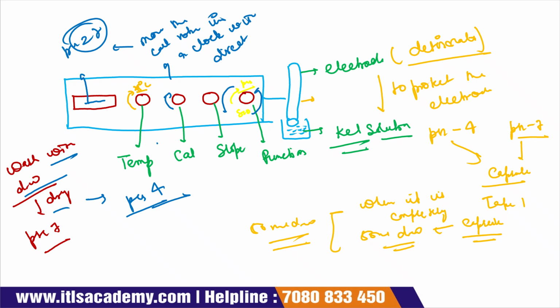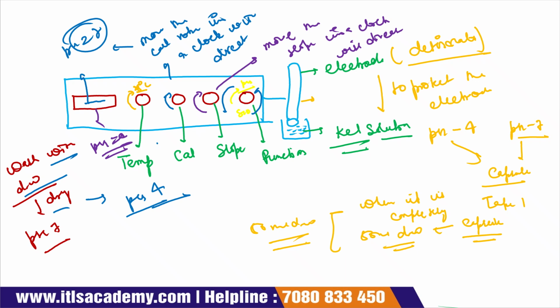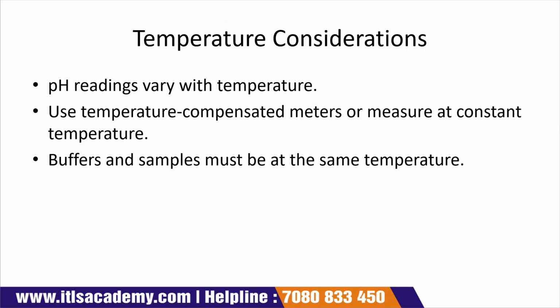Now what you have to do, you have to move the slope in a clockwise direction until you get pH 4. Now your pH meter is calibrated and it can be used for the measurement of the pH of the product. So this is how you calibrate it. The video related to this is already uploaded in our account. You can see that for better understanding. Now come to the next.